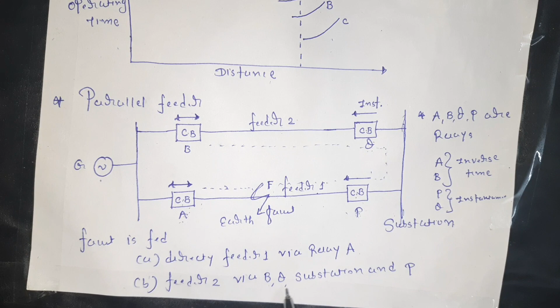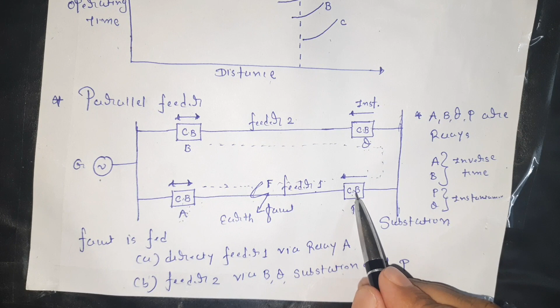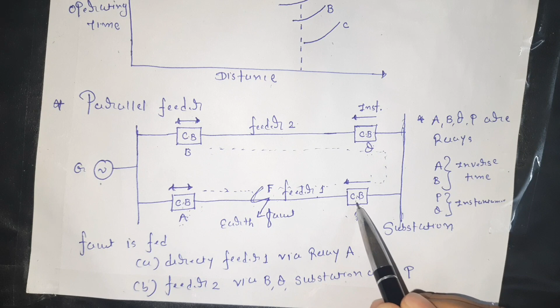Now the feeding of the fault via the path B, Q, substation and P will stop because this circuit breaker will operate. So this path, B, Q, substation, P and then fault, will stop. So current at B becomes normal and the relay at B is not operative. That is why this relay is non-operative.